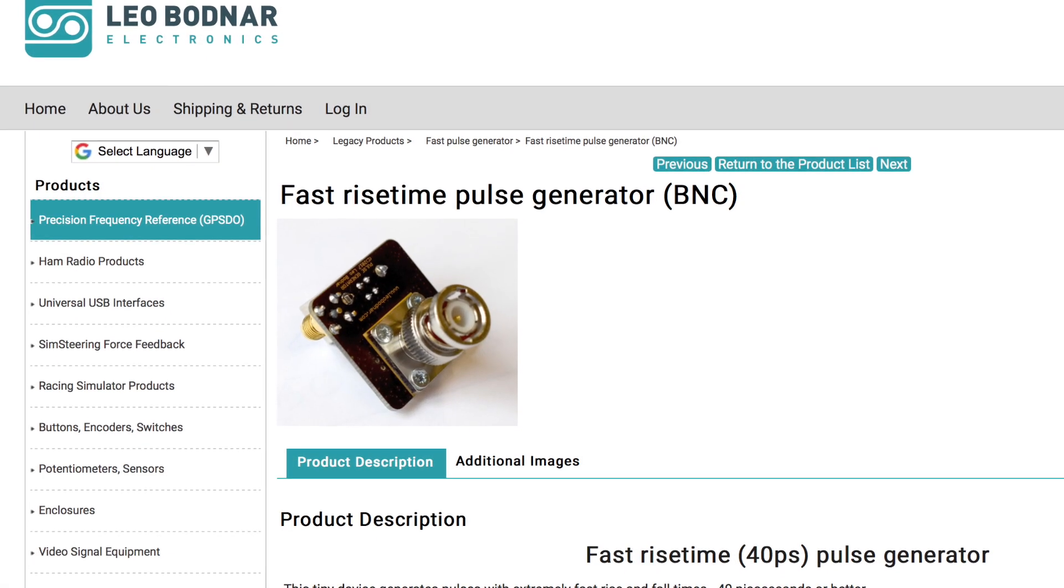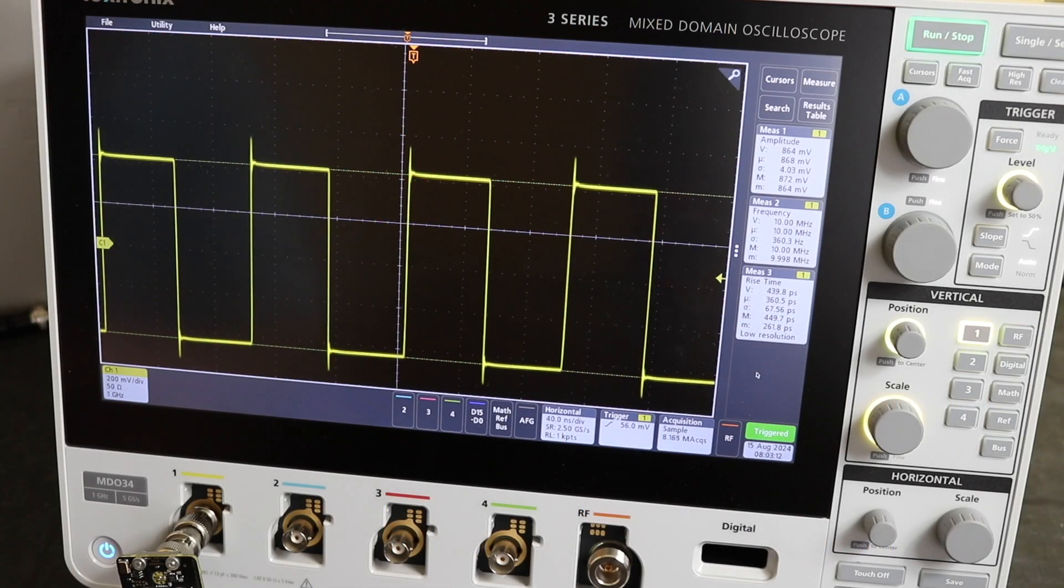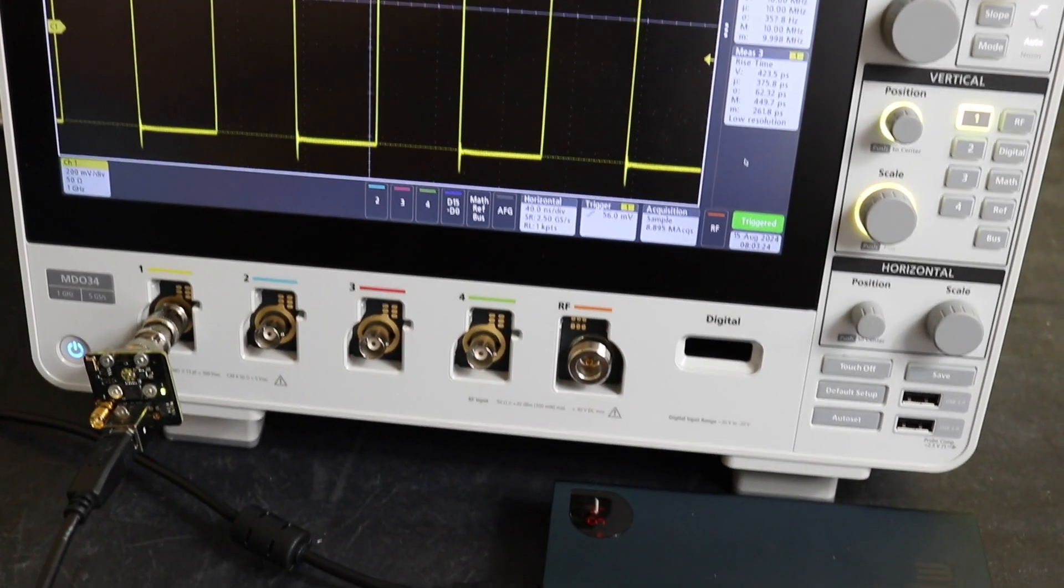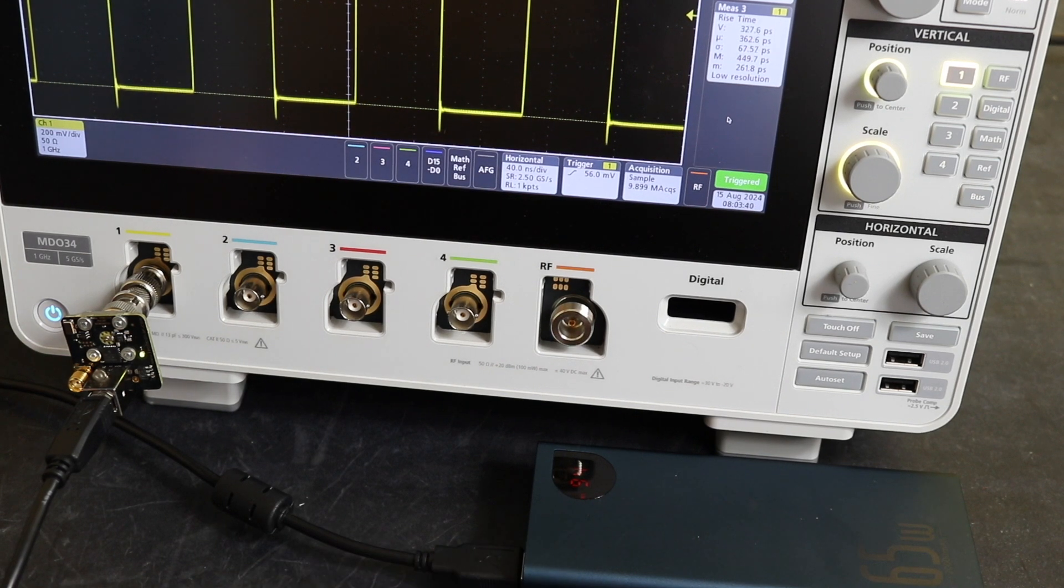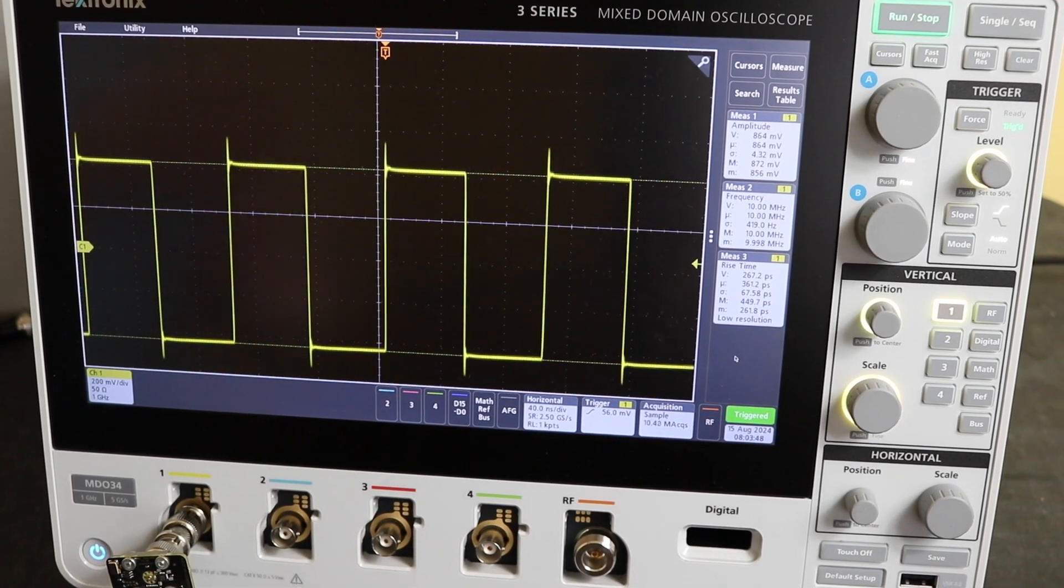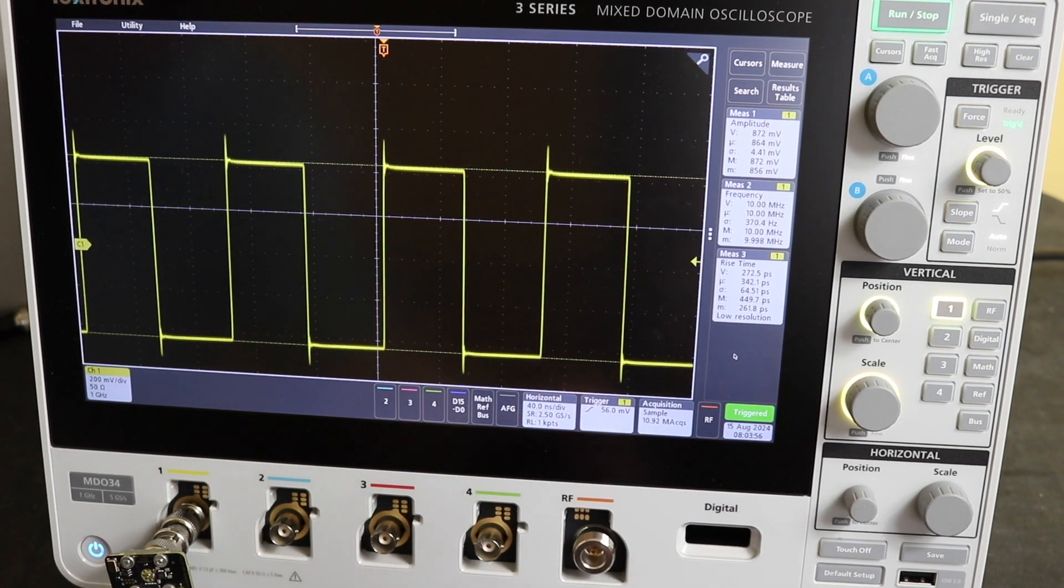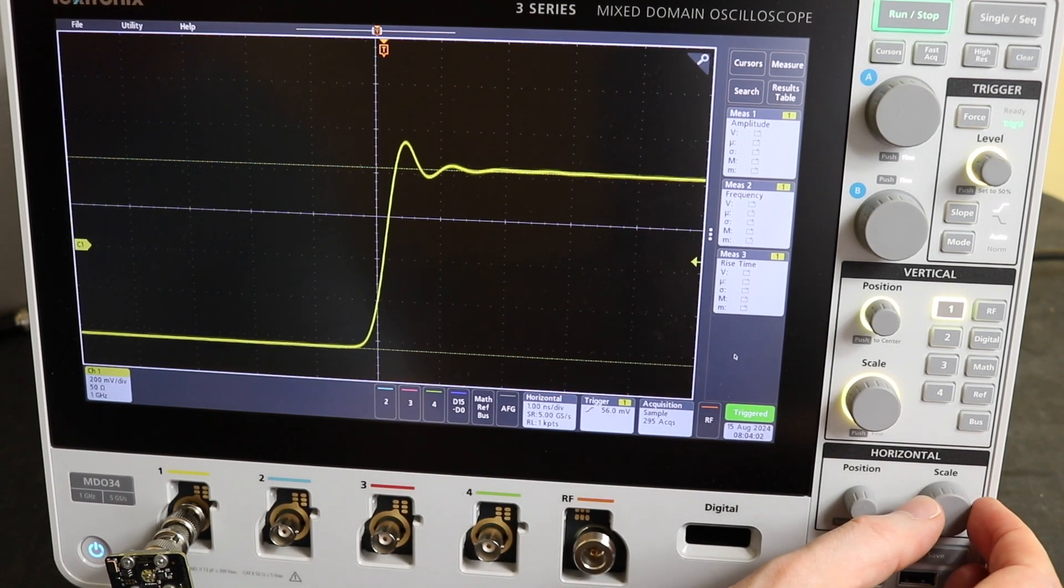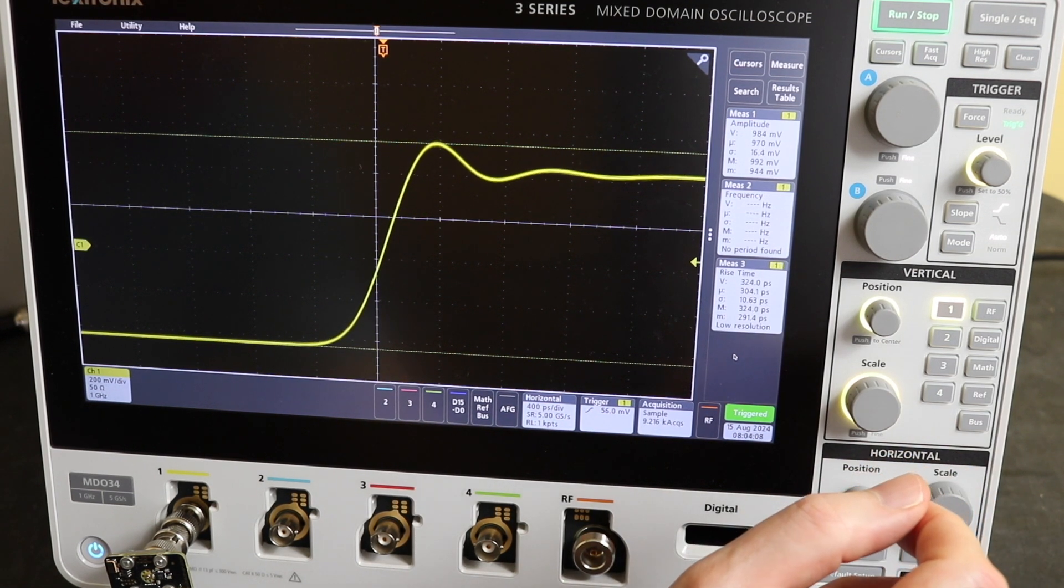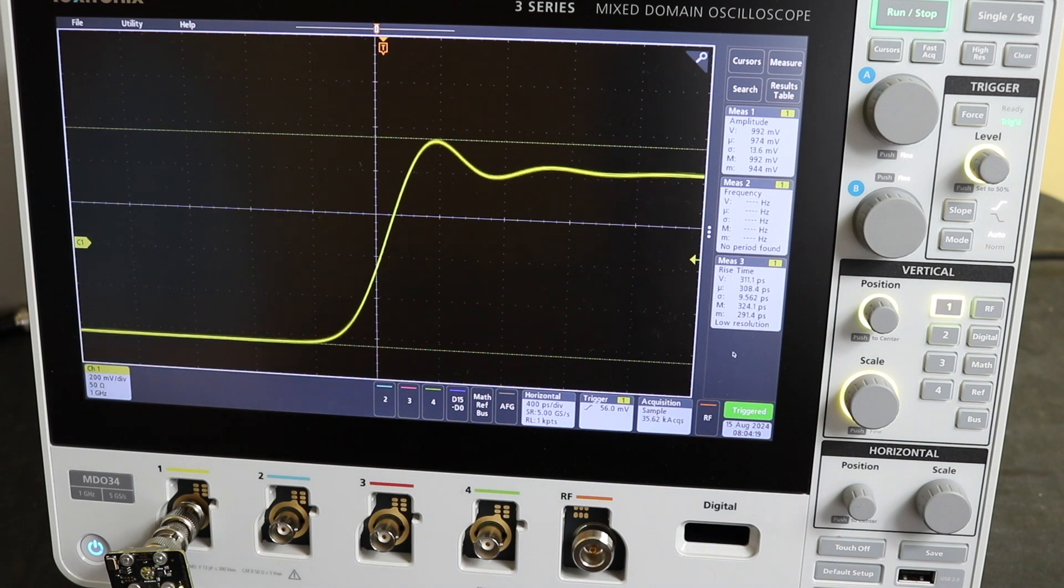This is from Leo Bodnar Electronics. It's a very fast rising pulse which is typical of an actual partial discharge pulse, so it's also emulating that a little bit. Only it's a square wave and it's just powered from a USB power bank here. You can see the actual pulse injection unit there and my USB power bank providing the power to it. The scope is just at a slight angle to stop reflections. That's the pulse. I can get the amplitude and the frequency from that. I do get a rise time measurement but to get it properly we need to expand out on the horizontal scale there and then you can see you get a bit better, less deviation shall we say, in the actual rise time measurement there. So I'll add that into the measurements that I have made.